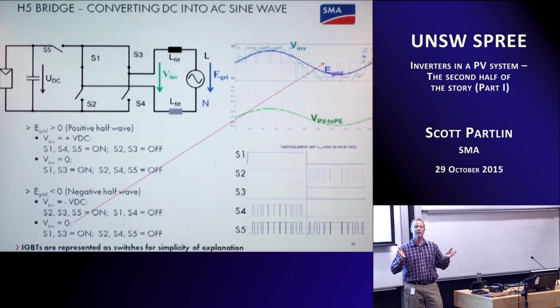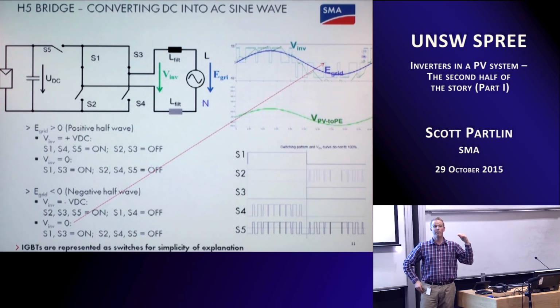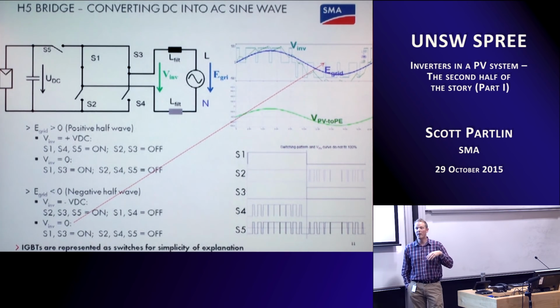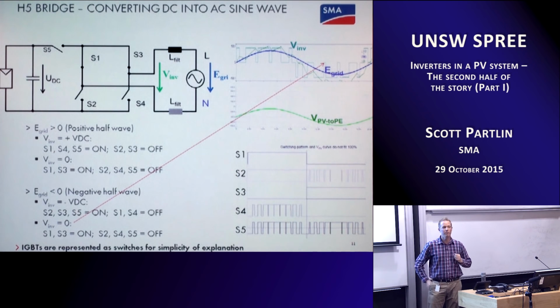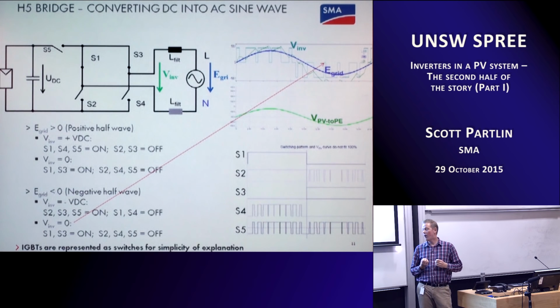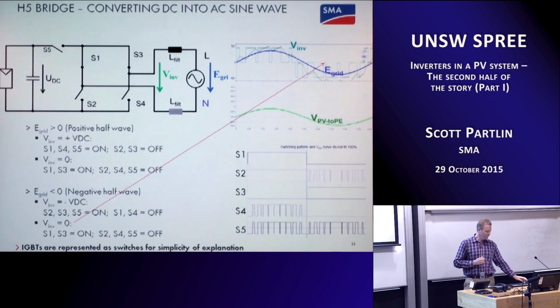So there might be a 500 volt DC string. The 500 volts will always remain, but it may be that at one point in the cycle, that maximum voltage has 500 volts down to Earth, whereas at another point in the cycle, the maximum may be, say, 250 volts to Earth, and the maximum negative could be negative 240 volts with reference to Earth. And for those of you that have a good appreciation of PV and some of the reliability issues that can arise, you'll automatically see that that gives rise to conditions that can cause PID, potential induced degradation. So, and that's something I'll cover a little bit more in the talk next month, or I can answer questions about it later.